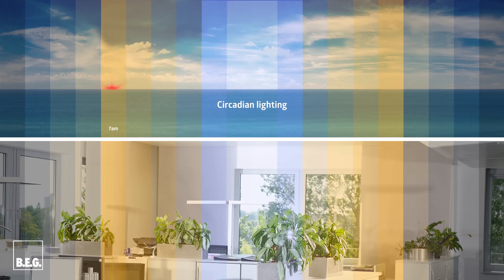The circadian lighting is based on a natural day-night rhythm. In the course of a day, the biological effective lighting varies. Not only the color temperature changes from warm white to cool white, but also the luminosity of 500 to 1500 lux adapts to the circadian rhythm of human beings. Clear differences can be seen in the light temperature of cool white at approximately 5700 Kelvin, white at about 4000 Kelvin, and warm white at approximately 3000 Kelvin.